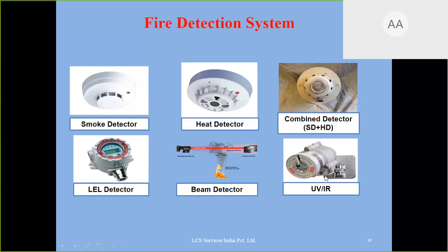In case of ultraviolet rays, if something happens due to anything, like a spark, it will catch it and tell you. There is a system which will take care of it: it will give you an alarm, the UV-IR sensor, and if there is an automatic system, then gas will be dumped. If it is manual, then you have to control it. So all this is a fire detection system: smoke detector, heat detector, combined detector, LEL, beam, and UV-IR sensor.